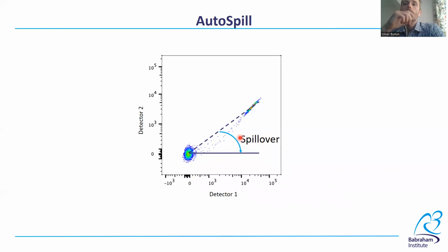When Carlos Roca, a mathematician, joined our lab, I sat down with him to discuss how to fix the issues we were having. He realized that the linear nature of quantum mechanics meant the spillover into the off-target detectors would be directly proportional to the signal in the main detector. As such, a linear regression along the slope would be a good strategy. This is the basis of AutoSpill.